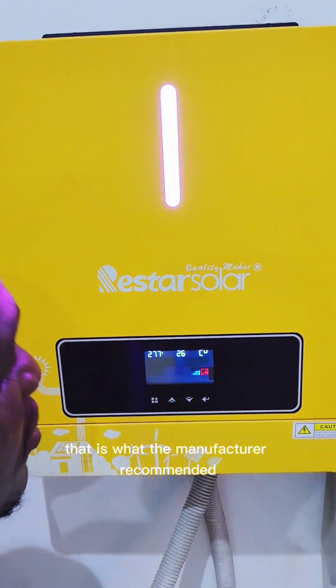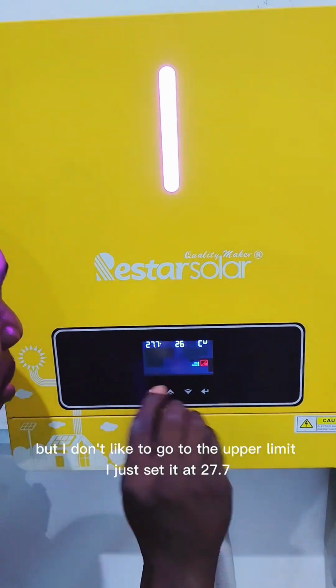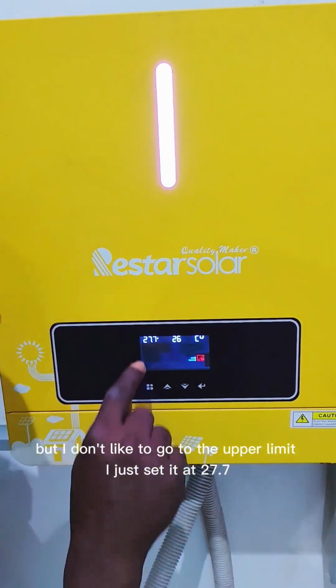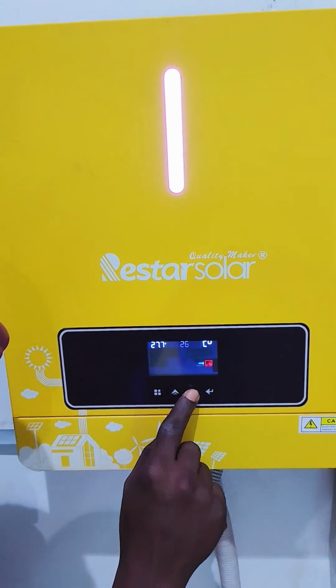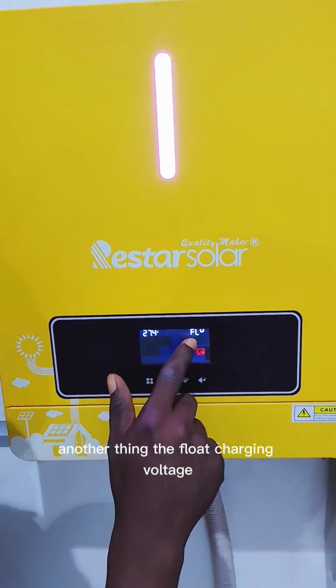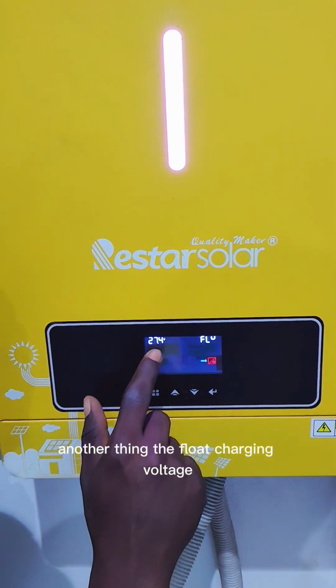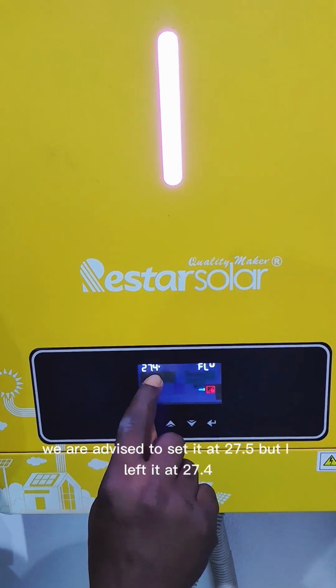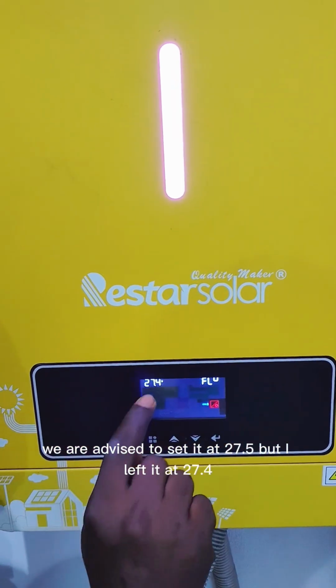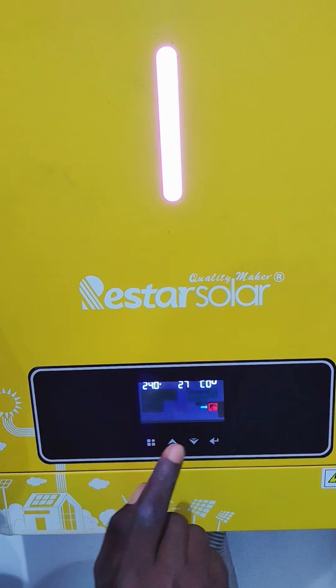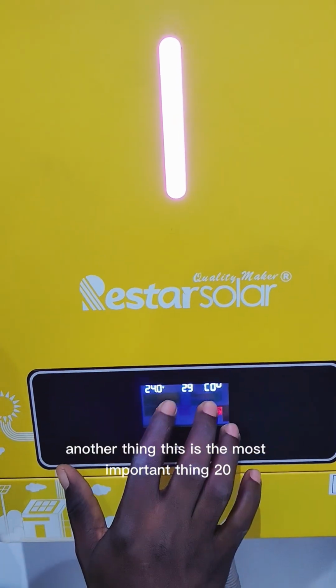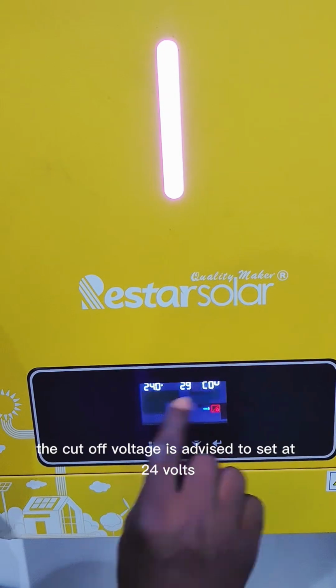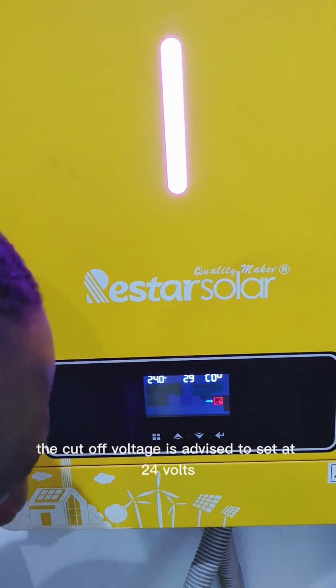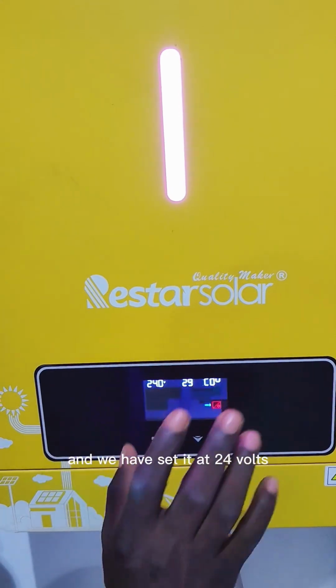That is what the manufacturer recommended, but I don't like to go to the upper limit. I just set it at 27.7. Another thing, the float charging voltage, we are advised to set it at 27.5, but I left it at 27.4. Another thing, this is the most important thing, the cutoff voltage is advised to be set at 24 volts, and we have set it at 24 volts.